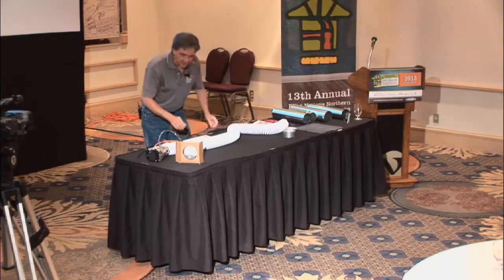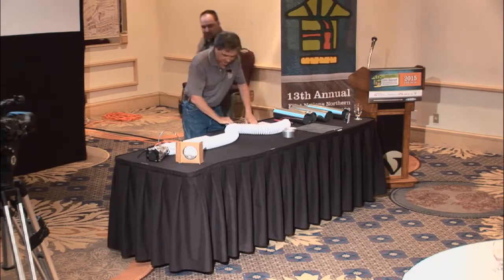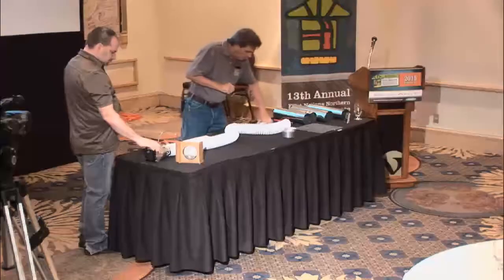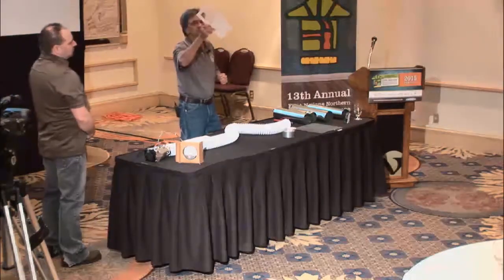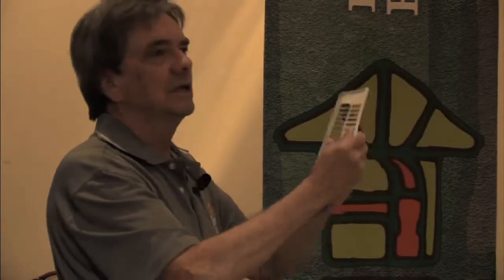Now the reality is, this louver actually blocks it up a bit. I think we've got a slide here that you'll see a photo. This is the louver I've got in my hand, and I bent these vanes straight just to show you. Now we're starting to manufacture them this way. They're hard to find, but they're straight on one side. You can see this well there. You see how you can see right through the clearance there?